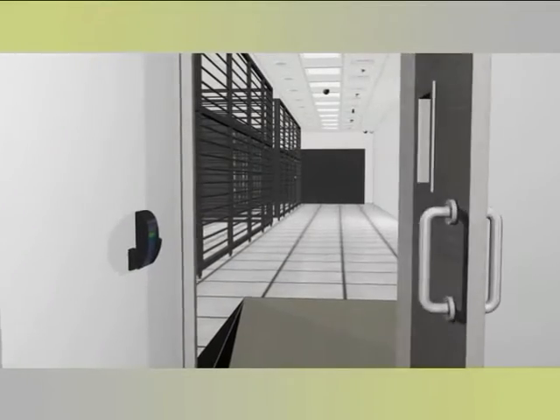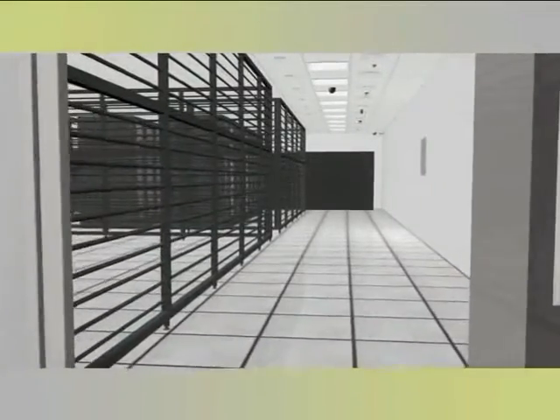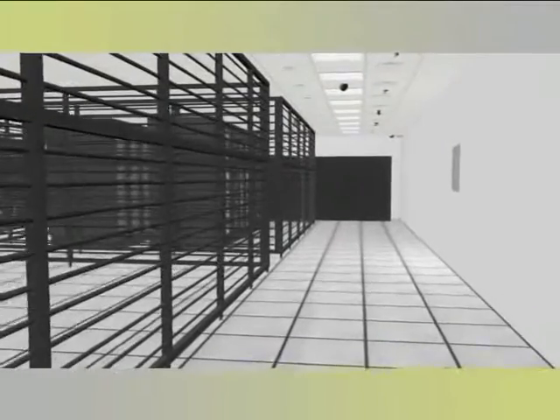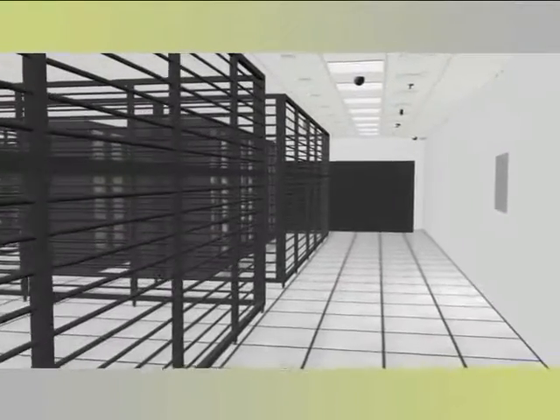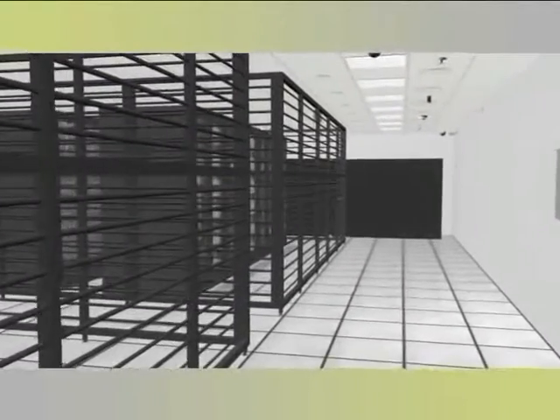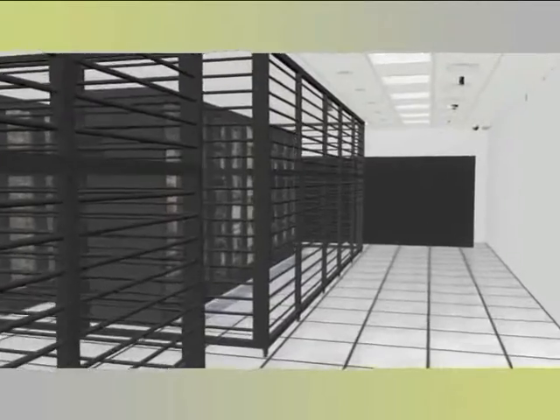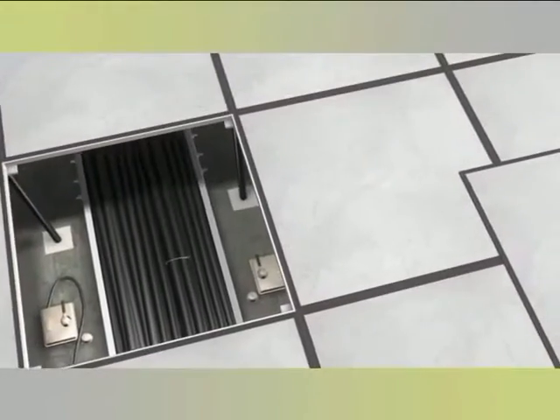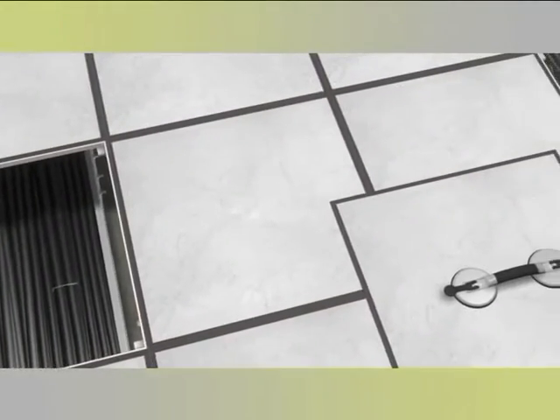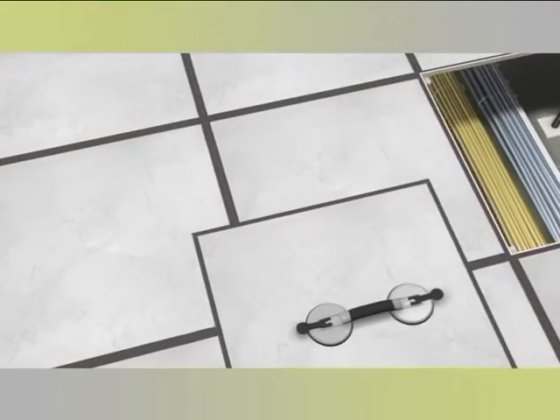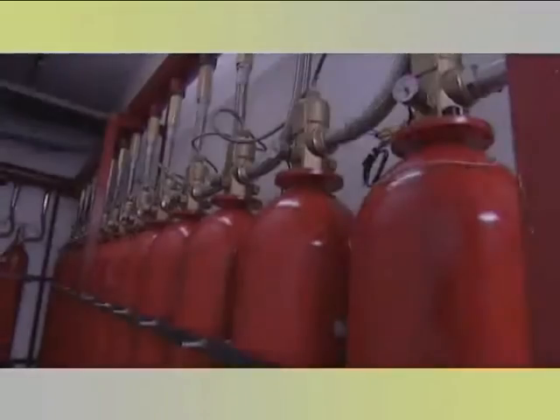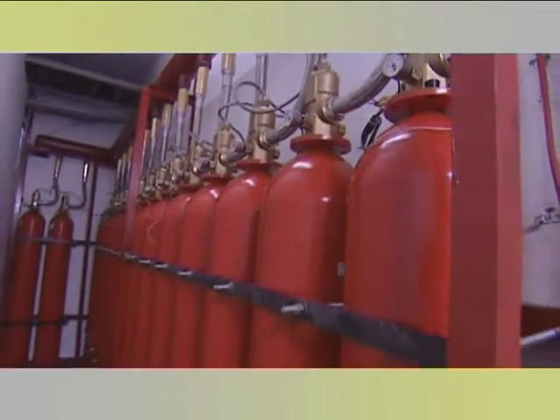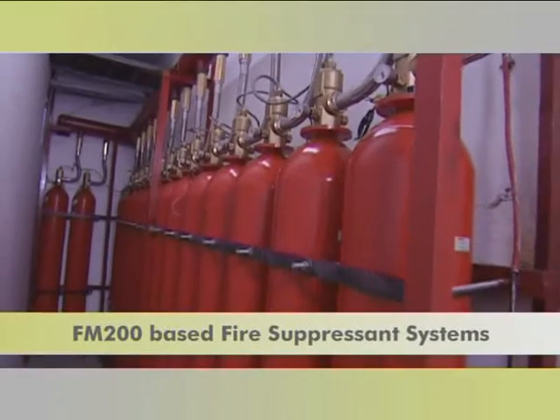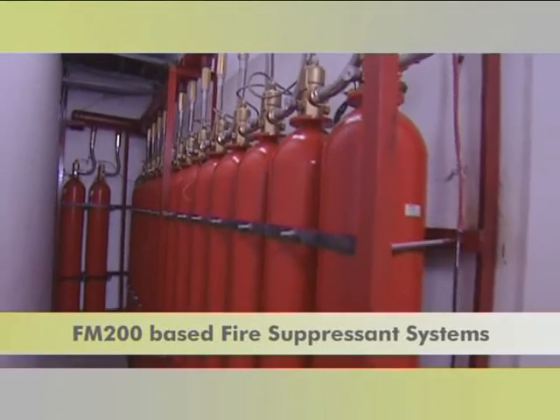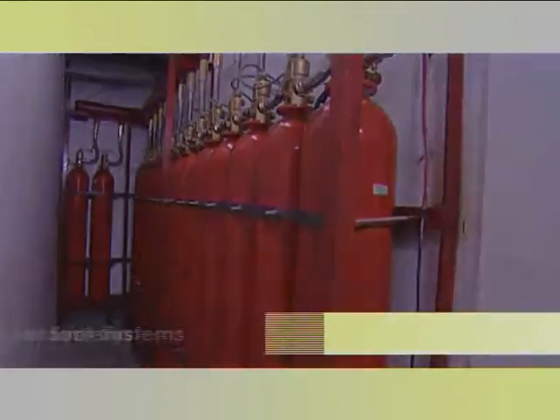A separate module in the server hall has been dedicated for clients who require a secured cage environment. Dedicated enclosures can be provisioned through the cage setup, thus creating a virtual data center area for clients. Separate raceways have been designed to carry data and power cabling. The facility is protected from fire hazards by FM200 gas-based fire suppressant systems integrated with VESDA.